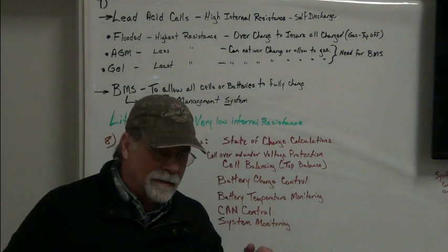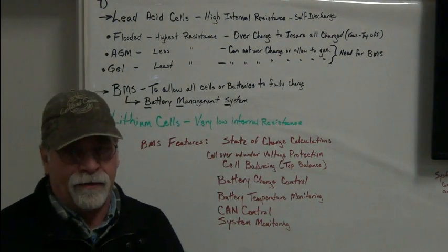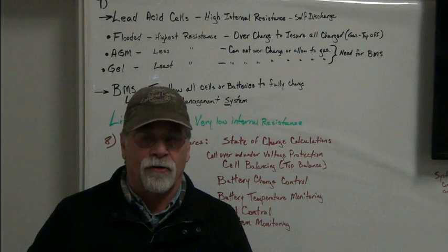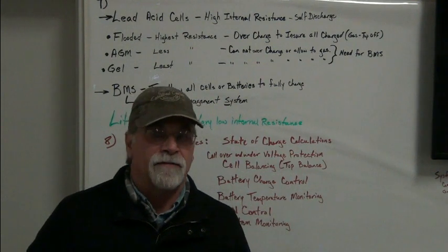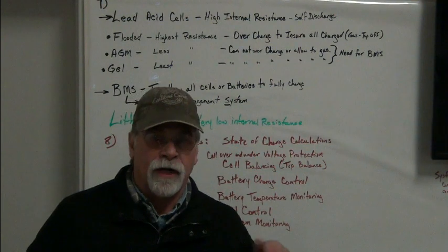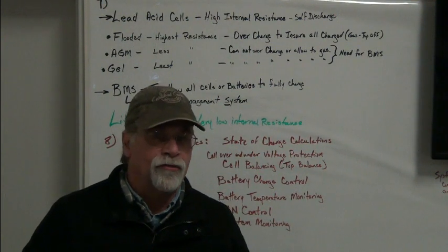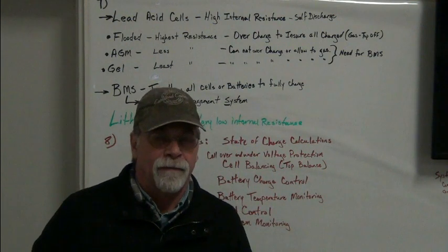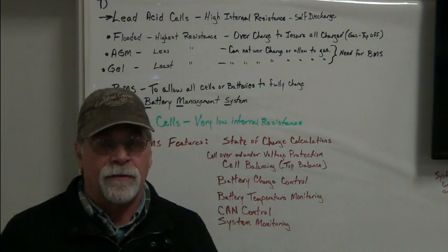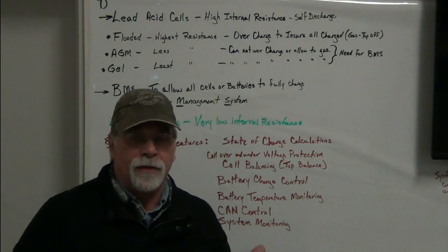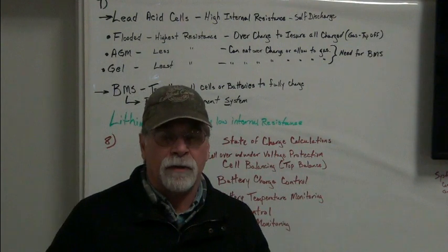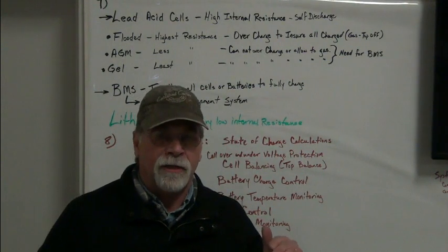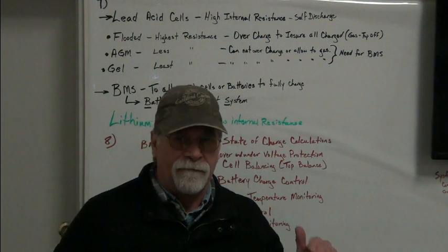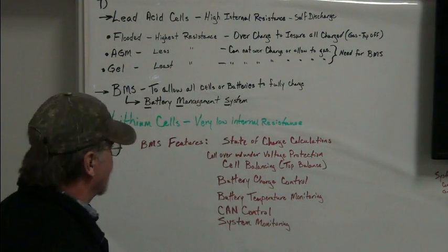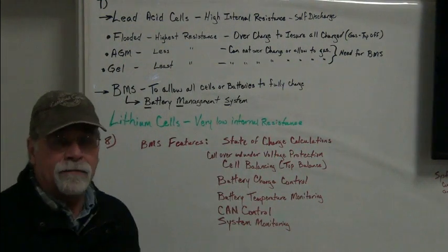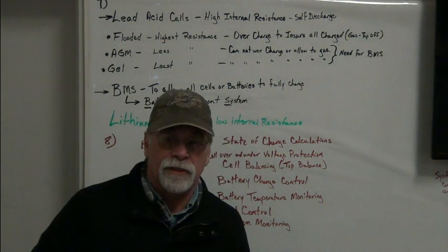One is depending on the chemistry. Some chemistries are much more sensitive to temperature, have a lower thermal runaway temperature, so those need to be monitored for safety reasons. And all lithium chemistries need to be protected from being charged at freezing or below. You never want to charge a lithium chemistry cell that's at freezing or below. That's another function most BMSs will do.